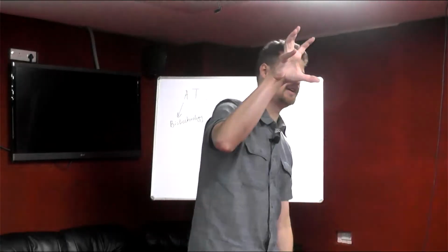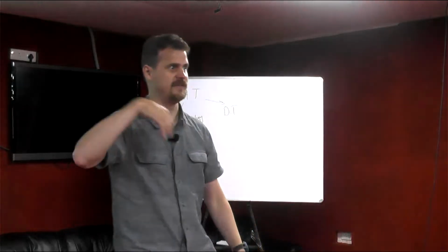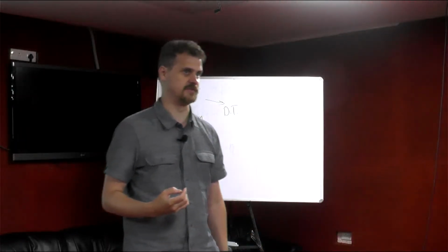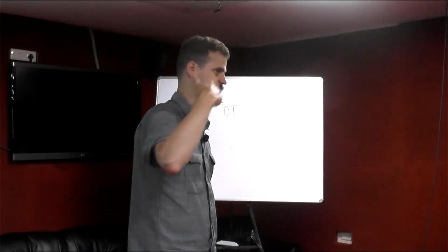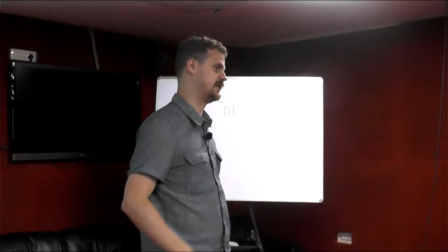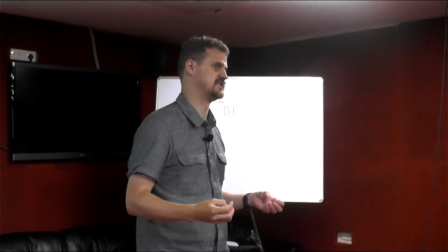But basically, if we talk about the general approach, the wearable artificial kidneys, on a very broad generalization, are basically the continuation of peritoneal dialysis or hemodialysis to some extent. So we introduce the dialysis regeneration unit that provides continuous regeneration of the spent dialysis fluid, and that gives us the opportunity to reuse the spent dialysis fluid all over again without the need to constantly exchange it.